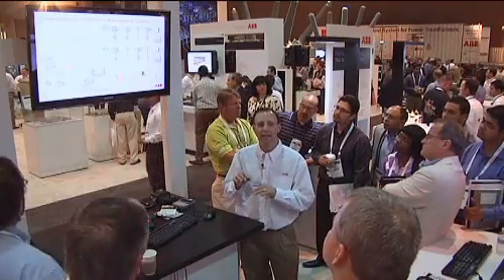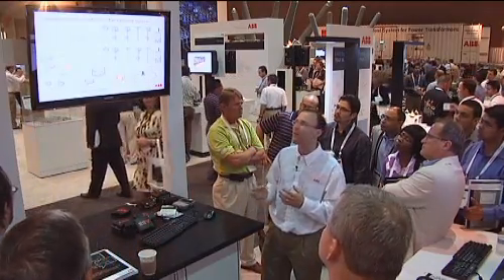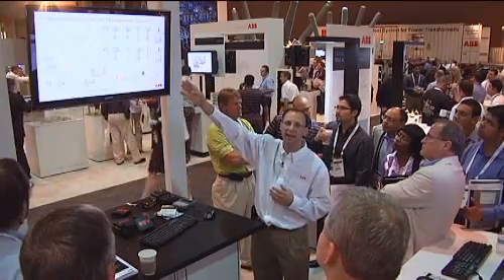And then we have users of that both in the data center, but outside of the data center, either at desktops of planners, of distribution engineers, and then technicians who can take their laptop to the field, and as they're servicing capacitors, they can actually monitor the system and verify the operation of the capacitor by operating a cap locally and seeing the effect of it at the head end of the feeder.